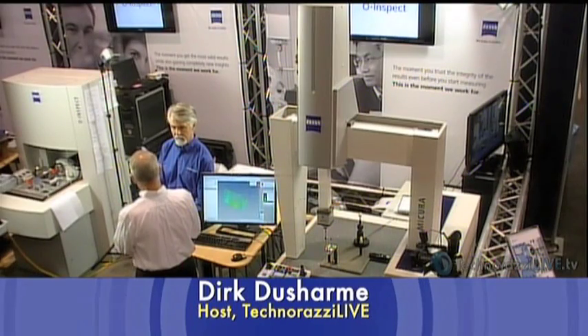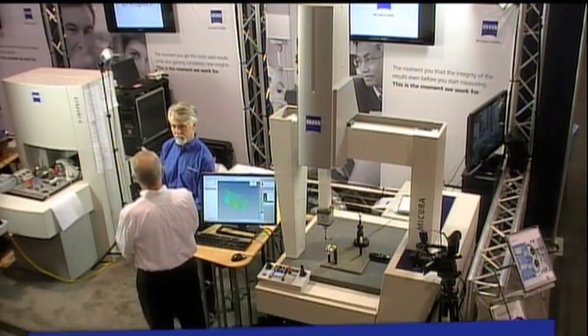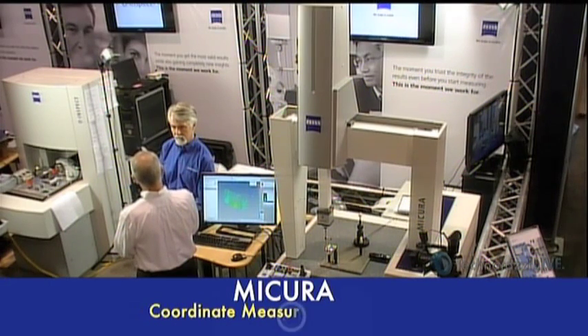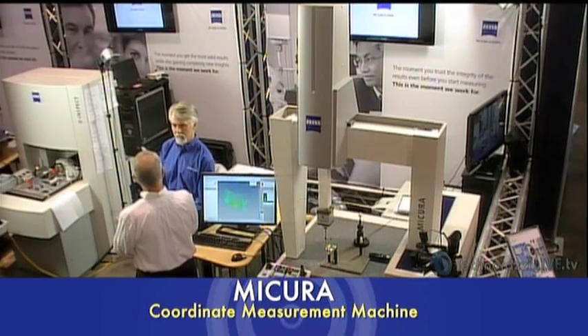How do you take accurate measurements when everything's kind of moving around? What's going on there? Well, Dirk, the design of the machine, we use the ceramic ways. We have four-sided air bearings that encompass the ways. All the rigidity, stiffness is built into the system. It isn't just the table moving, the whole system moves unitized.